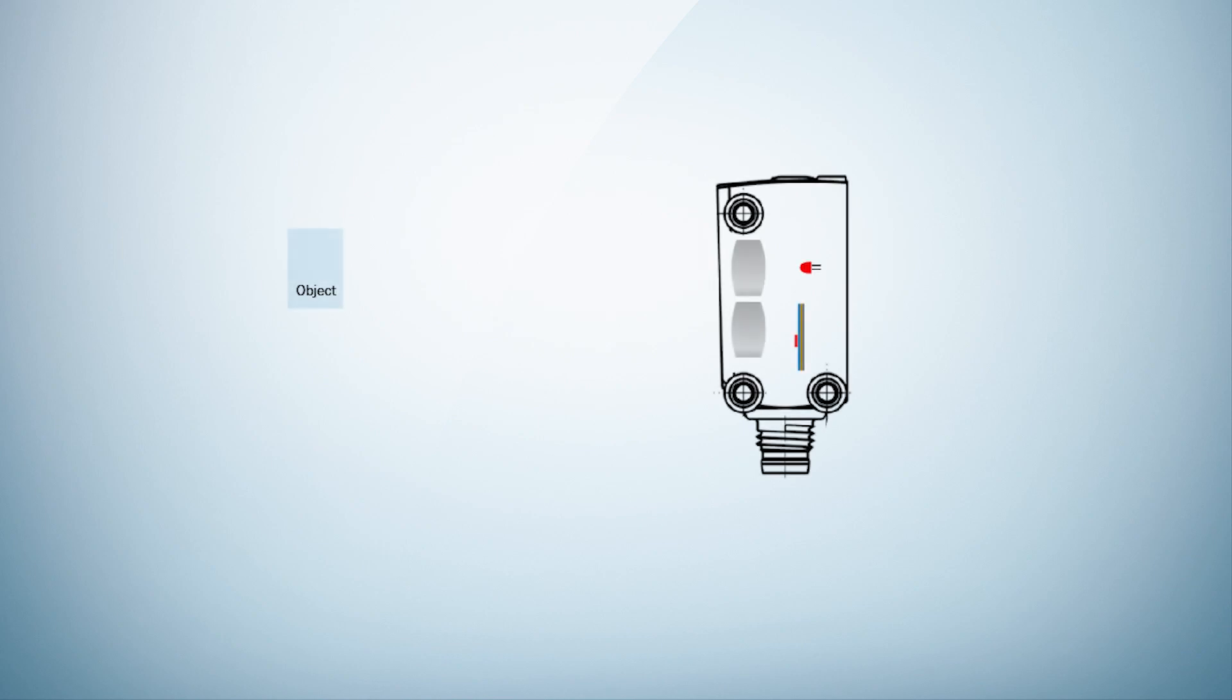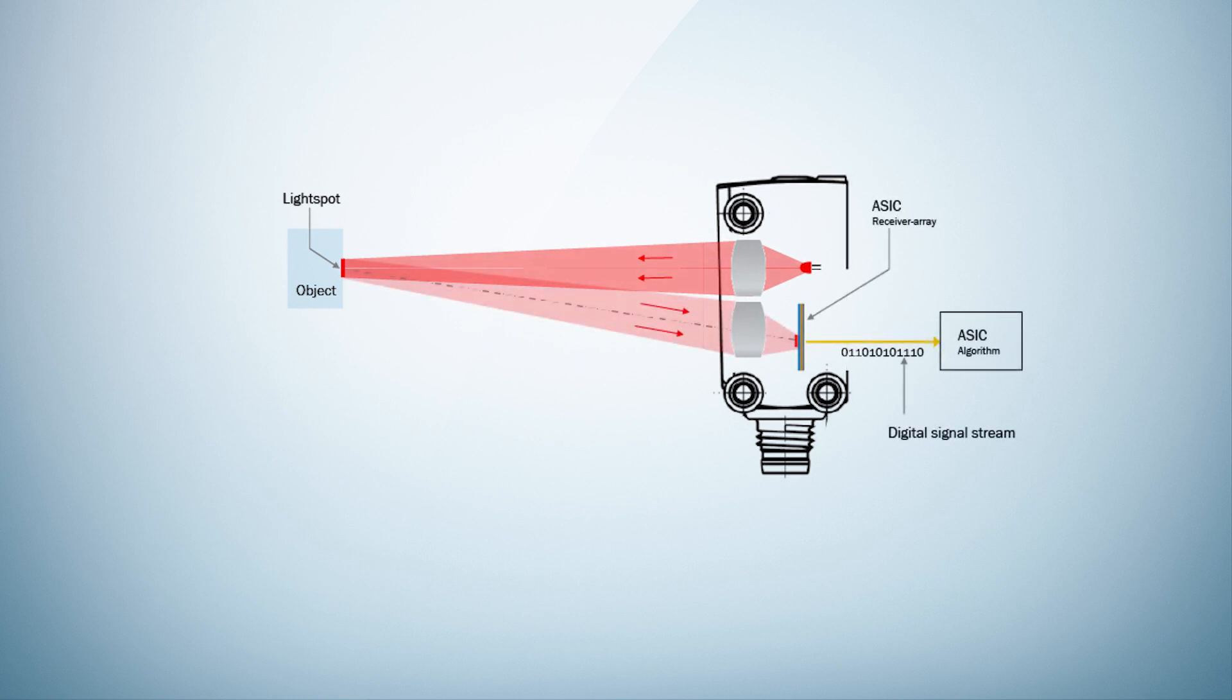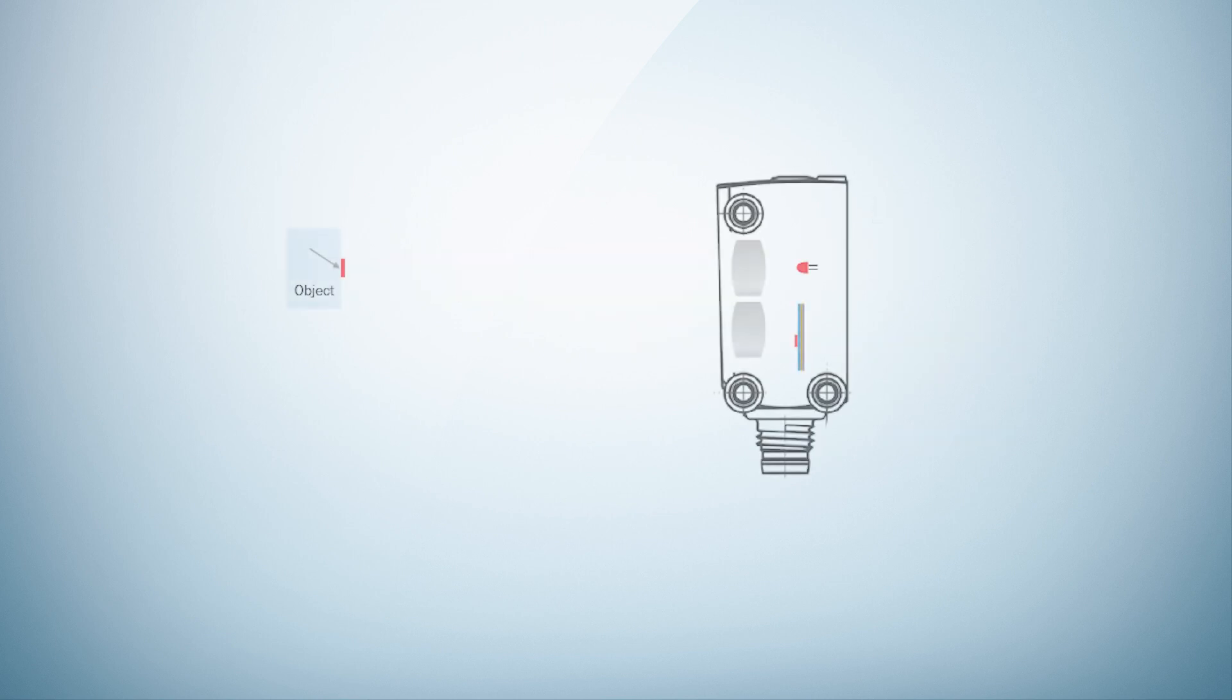In the sectional view of the W4S we see the operation of a photoelectric proximity switch with background suppression. With the pinpoint emitting LED and the emitting lens, a sharply defined light beam is generated which produces a light spot on an object. This light spot is imaged backwards by means of the receiving lens on the multipixel receiver array and it generates a photo current here. As already mentioned, this photo current is digitized directly at the pixel. The result is a digital signal stream that can be evaluated with special algorithms.